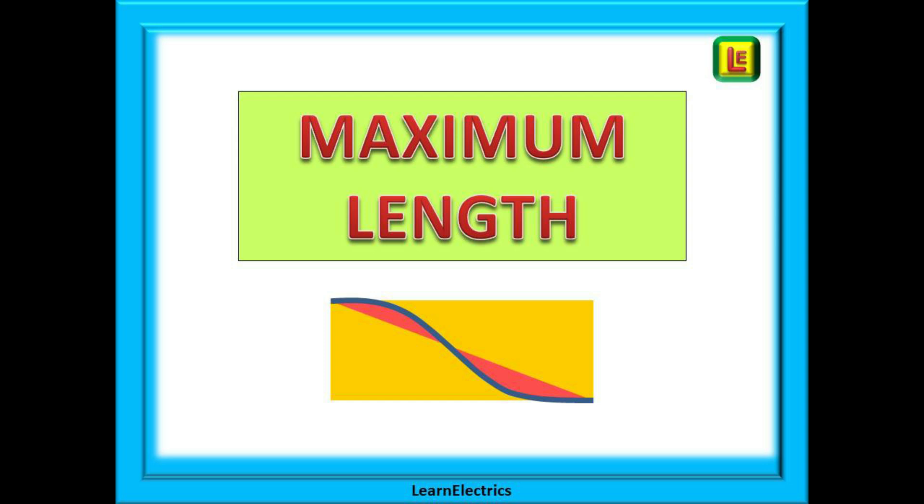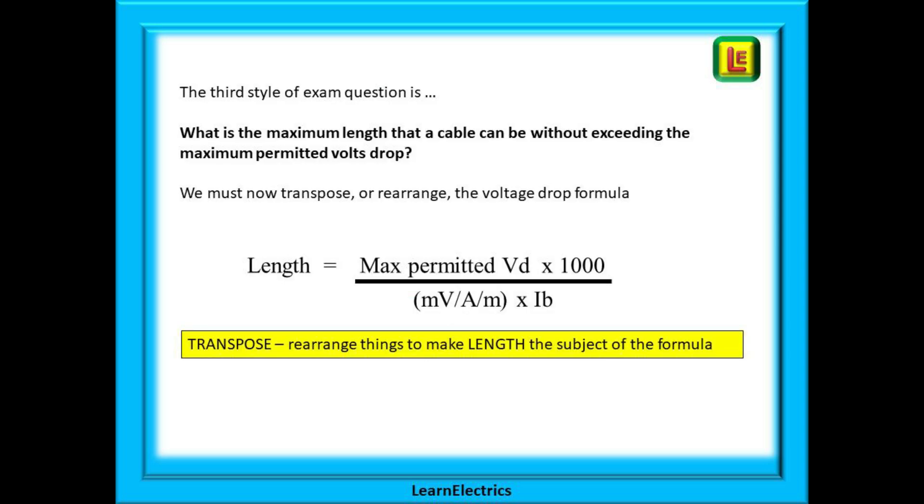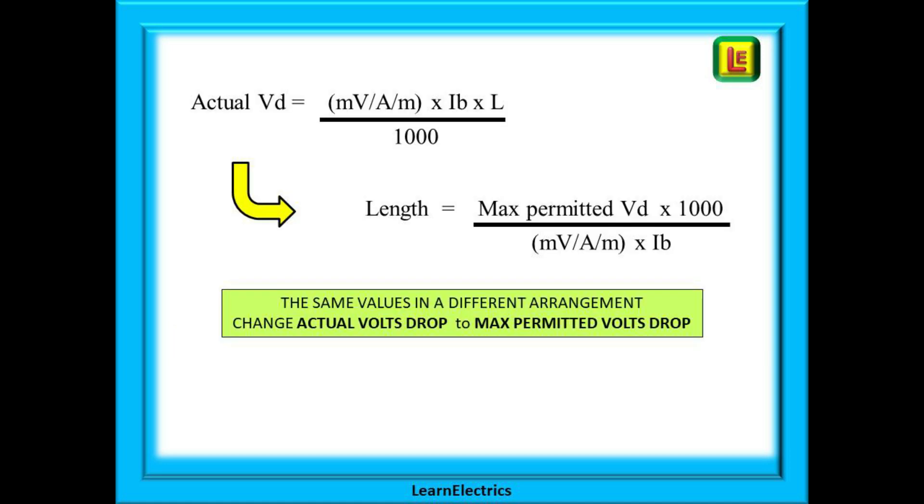Now we can move on to the maximum length of a cable. The third style of exam question is: what is the maximum length that a cable can be without exceeding the maximum permitted volts drop? We must now transpose or rearrange the voltage drop formula, and we show the new formula below. Here are the two rearranged formulas shown together. We are using the same terms but they have been transposed, and you will need to learn both formats. The important difference is that the actual volts drop has been changed to maximum volts drop. This will always be 6.9 volts for lighting and 11.5 volts for everything else.